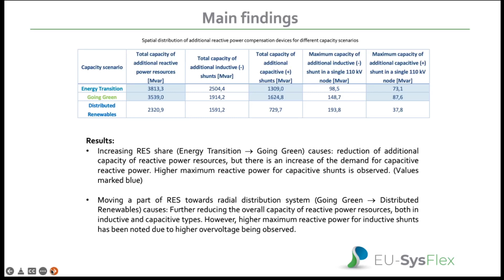As you can see, those maps present the spatial distribution of needs for shunt reactive power capacities for the different capacity scenarios: energy transition, going green, and distributed renewables. You can see that for the areas where under voltage problems occurred in the previous analysis, our algorithm proposed to install capacitor banks to mitigate those problems. Also, for the areas where we had serious problems with over voltages, the algorithm proposed a shunt reactor, which helped us to mitigate those problems, and hence we performed all those actions according to the installation of these devices.